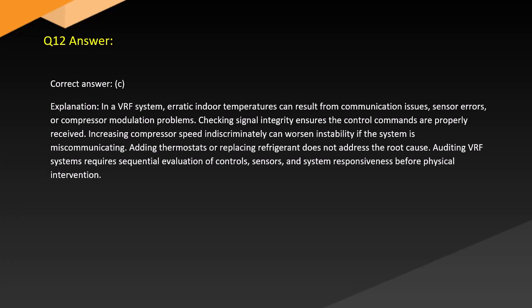Answer. Correct answer, C. Explanation. In a VRF system, erratic indoor temperatures can result from communication issues, sensor errors, or compressor modulation problems. Checking signal integrity ensures the control commands are properly received. Increasing compressor speed indiscriminately can worsen instability if the system is miscommunicating. Adding thermostats or replacing refrigerant does not address the root cause. Auditing VRF systems requires sequential evaluation of controls, sensors, and system responsiveness before physical intervention.